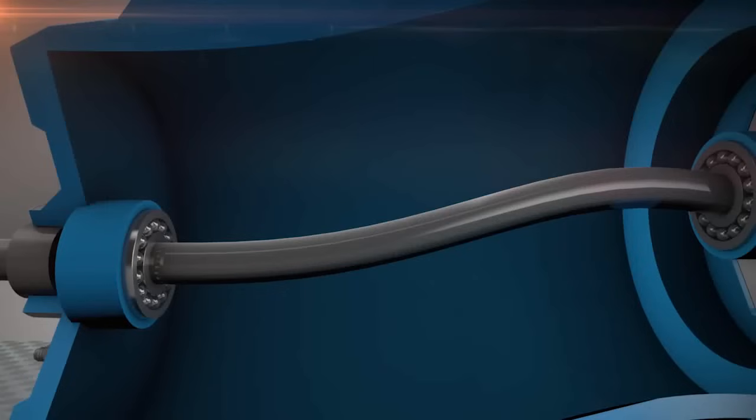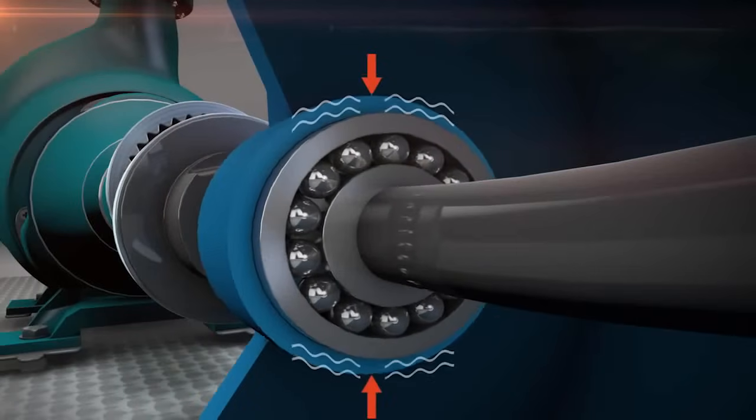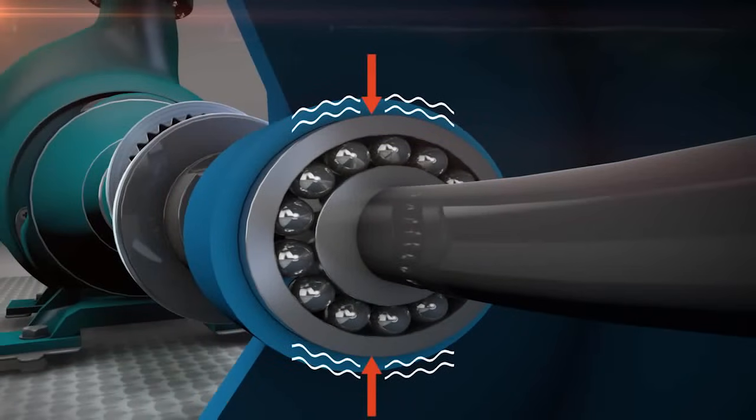Therefore, a soft foot condition creates two inflection points on the shaft, which produce vibration as the shaft rotates. The shaft doesn't like to be deflected, so it tries to straighten itself out.